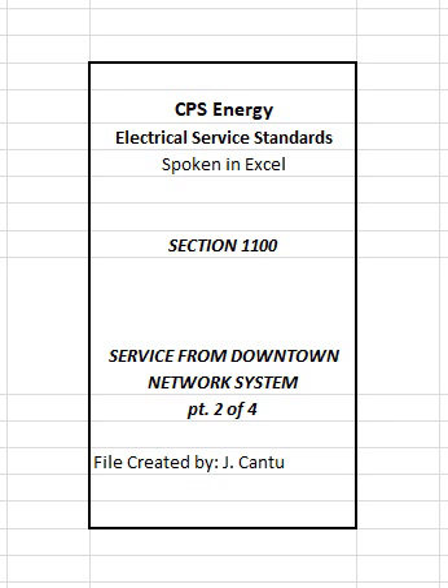3. CPS Energy will furnish and install ventilating fans and associated circuitry. 4. Ventilation openings shall be installed as far away as possible from doors, windows, fire escapes, and combustible materials. No ventilation openings to the interior of building are allowed. Openings outside the transformer vault or room shall be located above water level and not in the street, driveways, or parking lots.